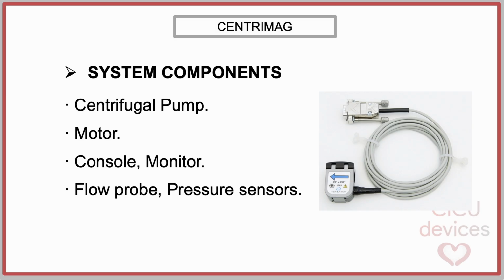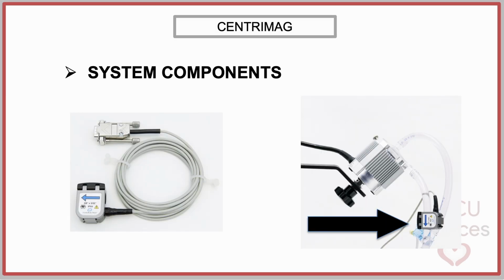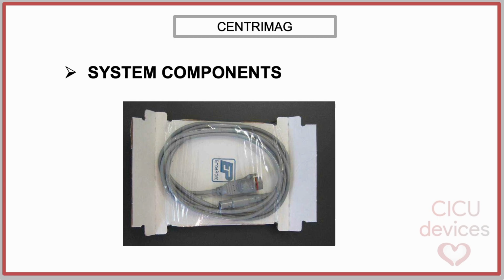Flow monitoring is typically performed using an external flow probe that provides continuous measurement of blood flow within the extracorporeal circuit. This sensor is typically positioned on the outflow tubing and operates using ultrasonic technology, allowing non-invasive flow measurement without direct contact with the blood. It also incorporates pressure sensors to monitor pressures through the circuit.